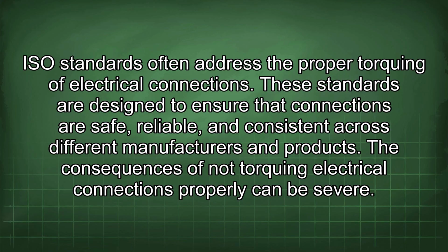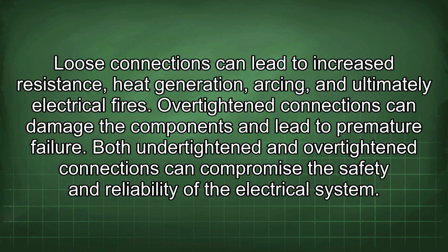The consequences of not torquing electrical connections properly can be severe. Loose connections can lead to increased resistance, heat generation, arcing, and ultimately electrical fires. Over-tightened connections can damage the components and lead to premature failure. Both under-tightened and over-tightened connections can compromise the safety and reliability of the electrical system.